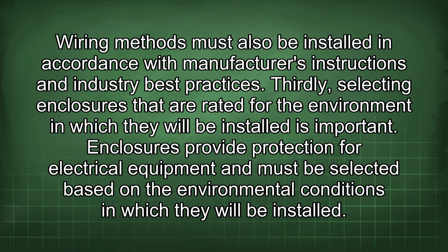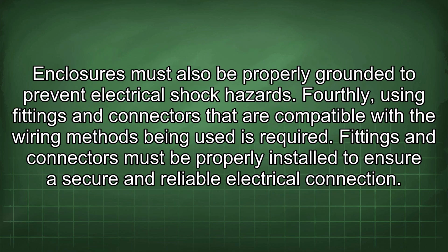Thirdly, selecting enclosures that are rated for the environment in which they will be installed is important. Enclosures provide protection for electrical equipment and must be selected based on the environmental conditions in which they will be installed. Enclosures must also be properly grounded to prevent electrical shock hazards. Fourthly, using fittings and connectors that are compatible with the wiring methods being used is required. Fittings and connectors must be properly installed to ensure a secure and reliable electrical connection.